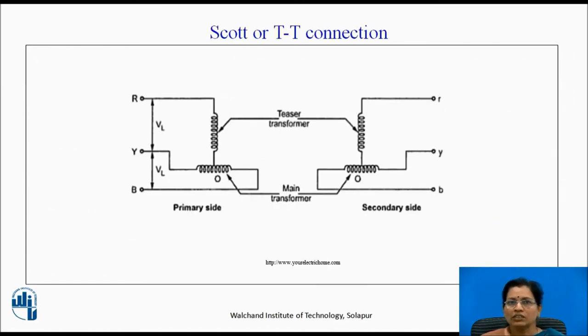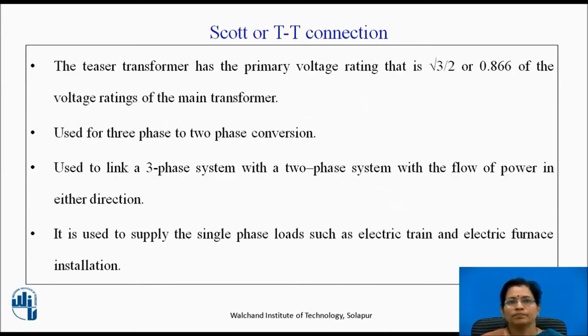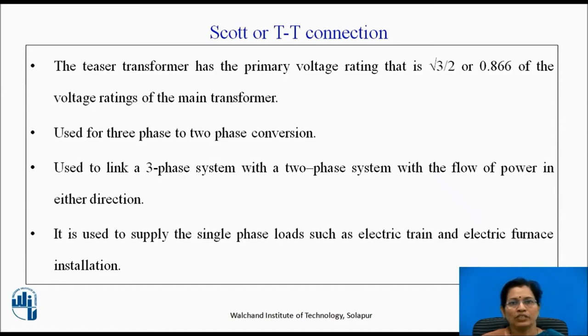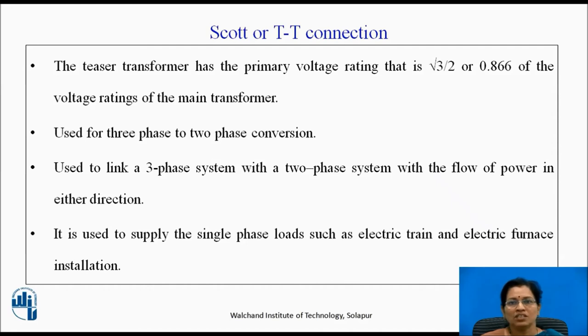This is the Scott connection. A teaser transformer and a main transformer are present. The teaser transformer has a primary voltage rating that is root 3 by 2 or 0.866 of the voltage rating of the main transformer. We can use this TT connection or Scott connection for 3-phase to 2-phase conversion. It is also used to link the 3-phase system with a 2-phase system with flow of power in either direction, and it is used to supply single-phase loads such as electric trains and electric furnace installations.